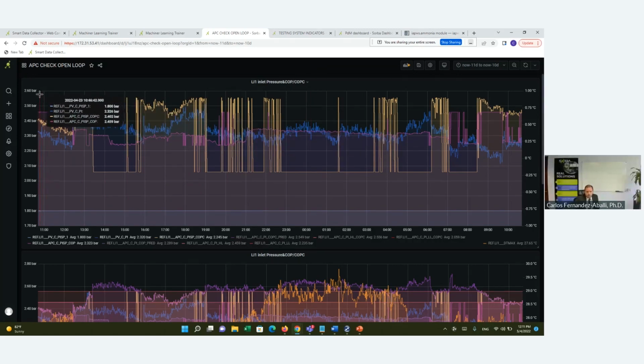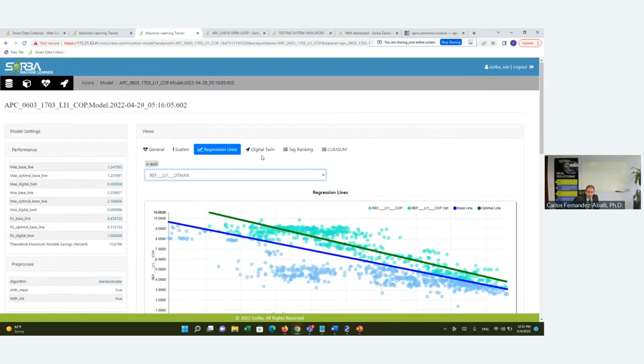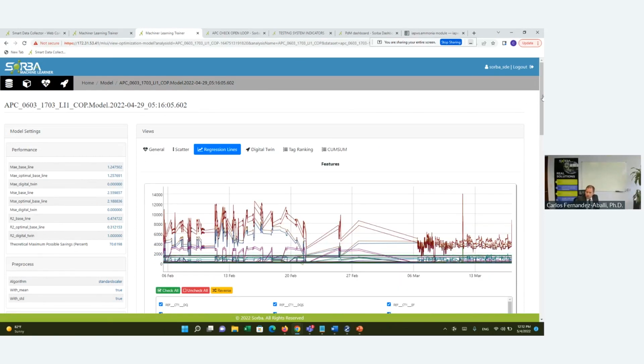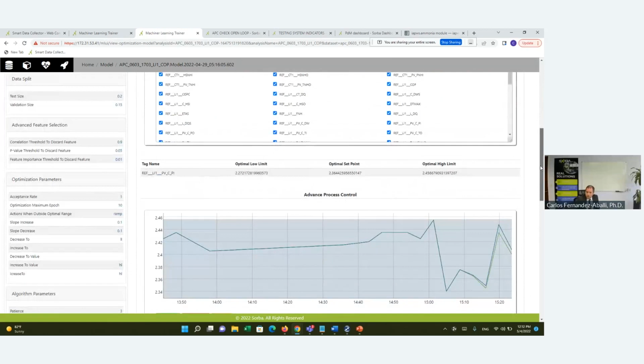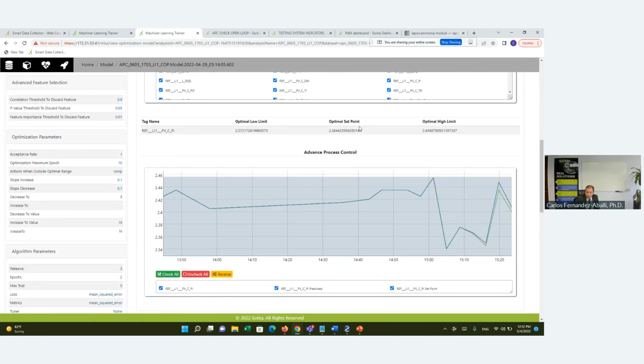And the answer is that the optimizer will only give a set point within an optimal high limit or low limit, which is determined during the training process. So if we go to the general parameters here, okay, it actually determines your optimal low limit, your optimal set point, and your optimal high limit. And your prediction, your real-time control, is happening between these two limits. If your process variable or your prediction exceeds these two limits, the system either enters into a ramp or jumps your set point directly to the mean. So it slowly brings your set point down, or brings it to the mean and to the bottom of your low limit, trying to bring the system back to behaving within the optimal bounds.